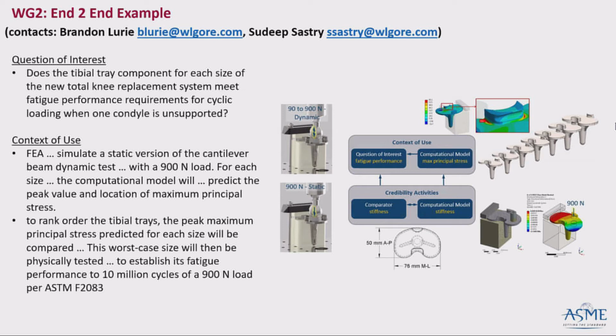So the question of interest is, does the tibial tray for each size of the new total knee replacement system meet fatigue performance requirements for cyclic loading when one condyle is unsupported? So it's a typical ASTM standard, I forgot which, I think it was mentioned here, ASTM F2083. So the context here is the model will use a static simulation to predict stresses, and based on the predicted stresses, we can rank order and determine what's the worst case. Again, as I said, it's a typical worst case selection. But it has a bit of a twist. I will explain that a little bit later.